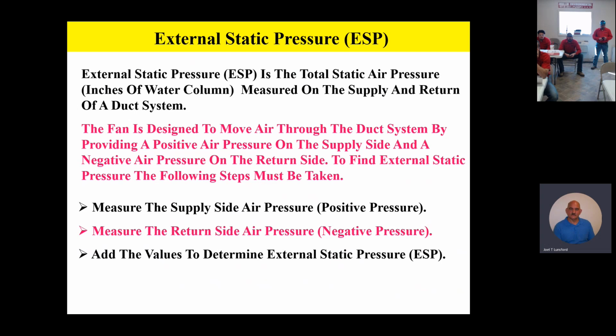Okay, so all of our factory airflow charts are set up for what we call external static pressure. Now, external static pressure is found by looking at supply static and return static. Remember, the fan is designed to move air through the duct system by providing a positive pressure on the supply side and a negative pressure on the return side.